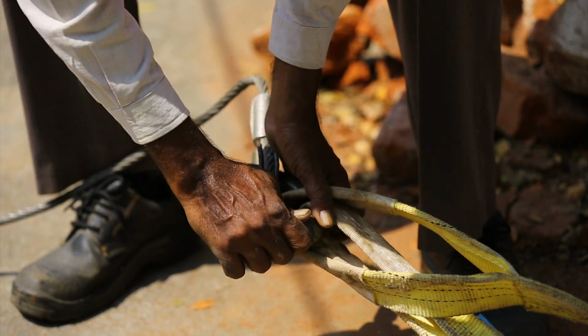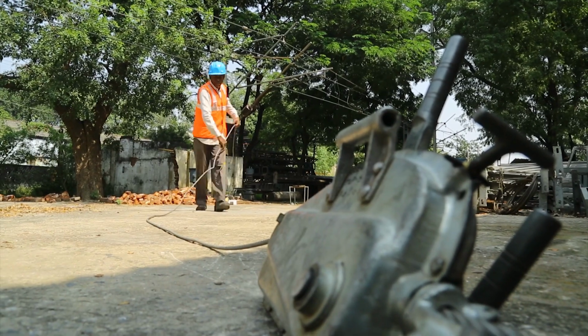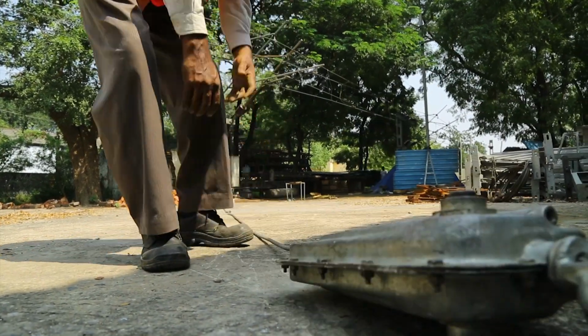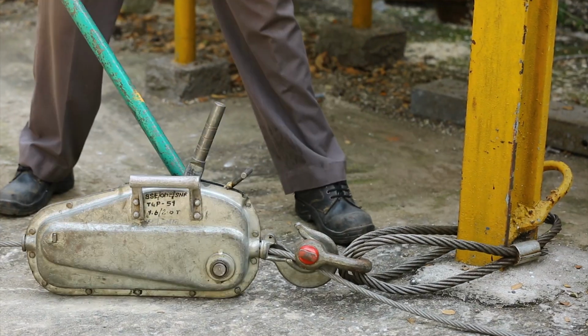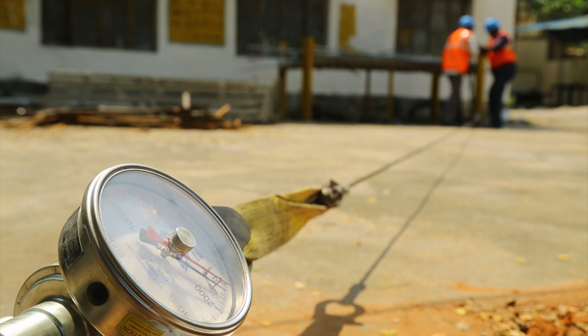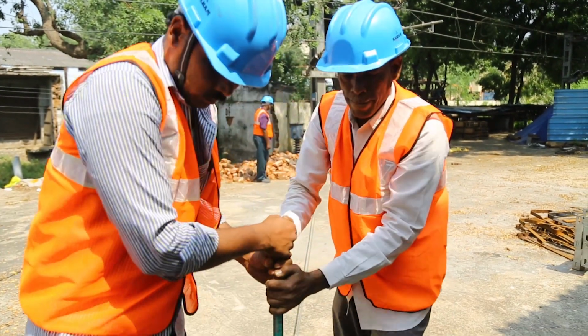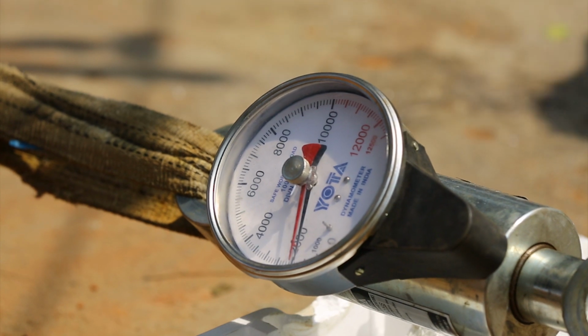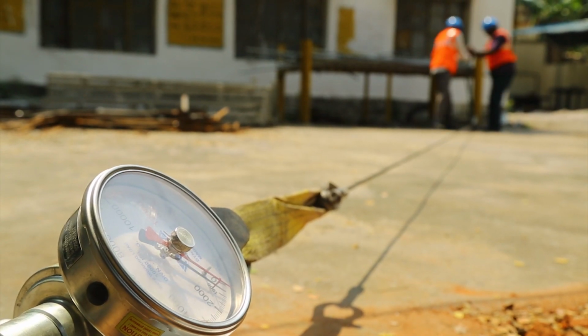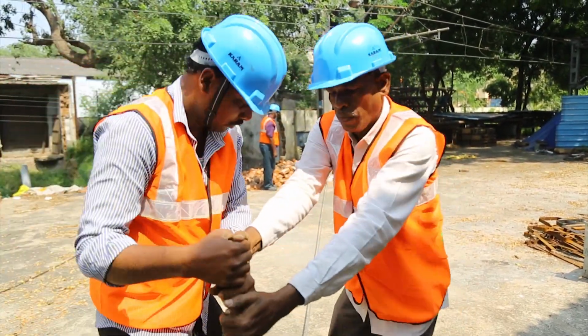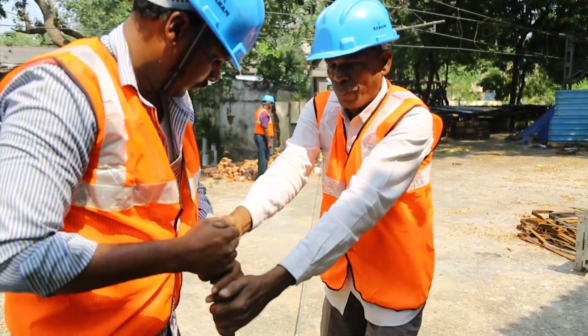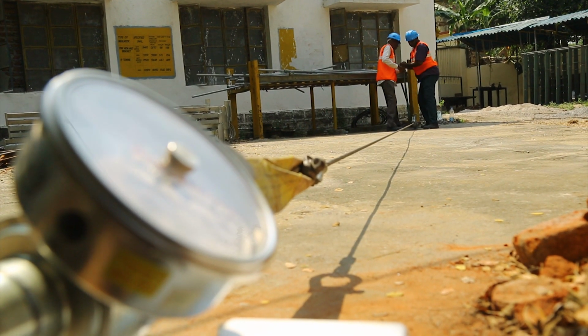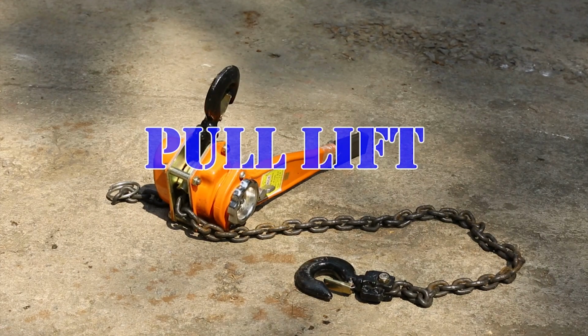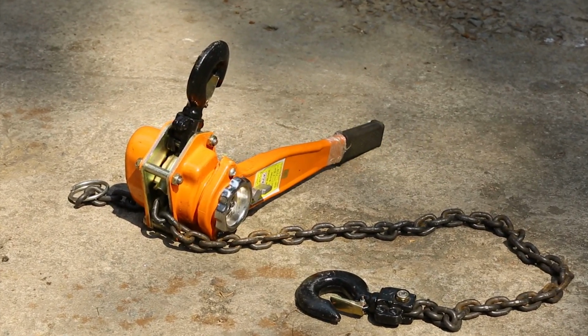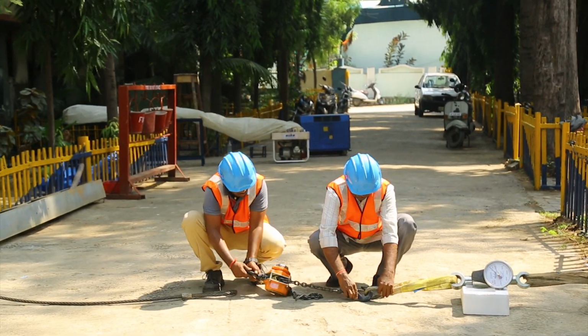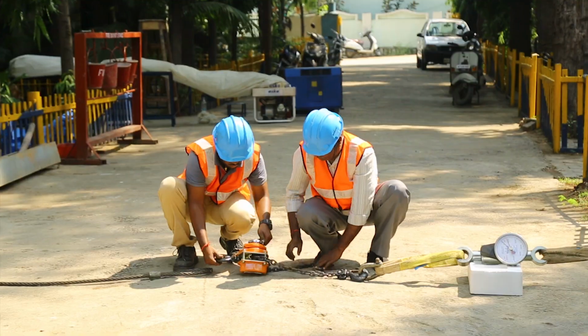A dynamometer is attached to TRD and gradual load is applied. Dynamometer shows the tension developed in the TRD and care should be taken that this does not exceed maximum value. Observation is made whether TRD withstanding the prescribed tension. Pull lift. Pull lift is used to take load and lift the OHE conductors in tension. Process of pull lift testing is same as that of TRD.